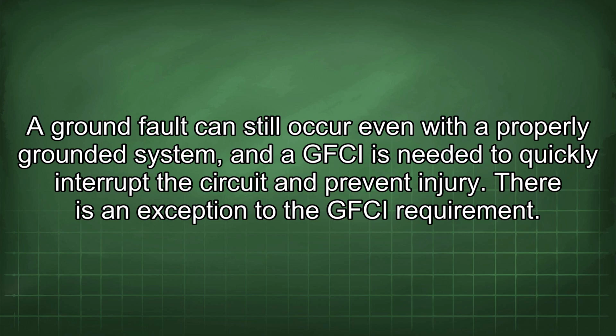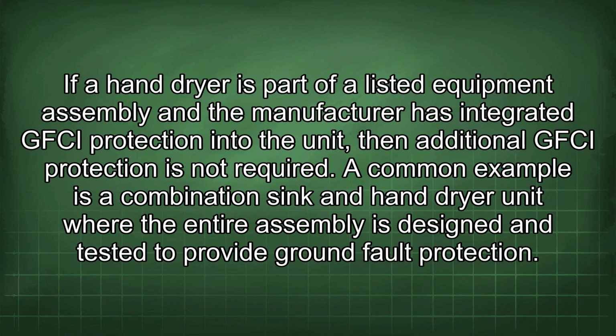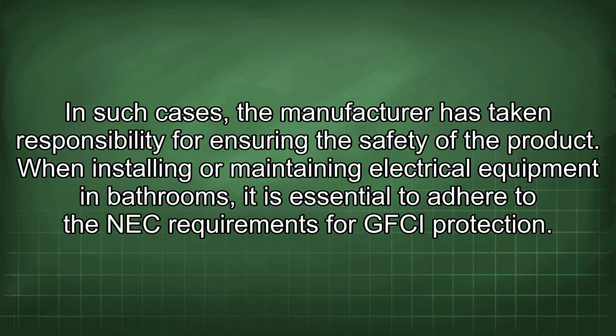There is an exception to the GFCI requirement. If a hand dryer is part of a listed equipment assembly and the manufacturer has integrated GFCI protection into the unit, then additional GFCI protection is not required. A common example is a combination sink and hand dryer unit where the entire assembly is designed and tested to provide ground fault protection. In such cases, the manufacturer has taken responsibility for ensuring the safety of the product.